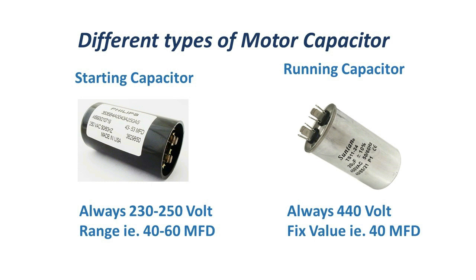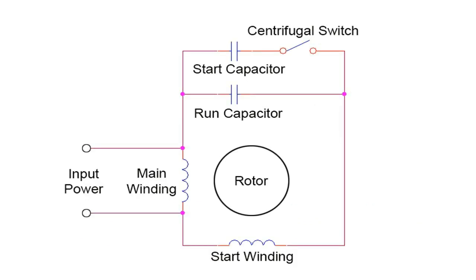Running capacitors have fixed values like 2, 4, 6, 10, 20, 30, or 50 MFD, and are always rated at 440 volts AC. By using a running capacitor in the motor circuit, it improves the power factor and reduces the current drawn by the motor.